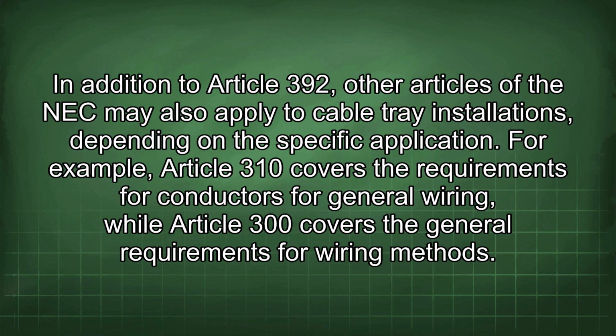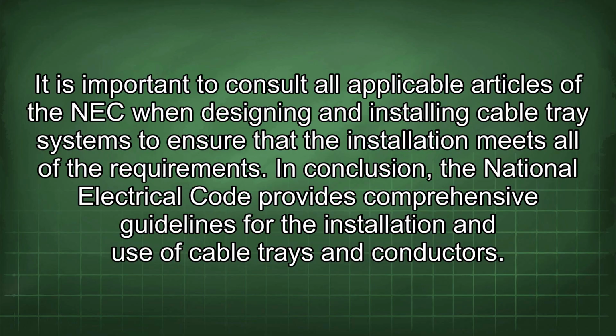In addition to Article 392, other articles of the NEC may also apply to cable tray installations, depending on the specific application. For example, Article 310 covers the requirements for conductors for general wiring, while Article 300 covers the general requirements for wiring methods. It is important to consult all applicable articles of the NEC when designing and installing cable tray systems to ensure that the installation meets all of the requirements.